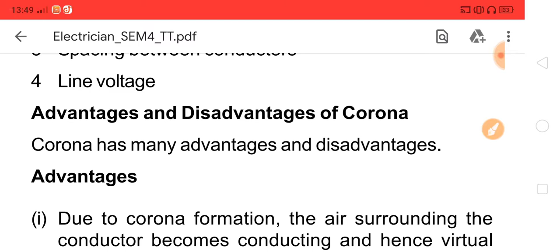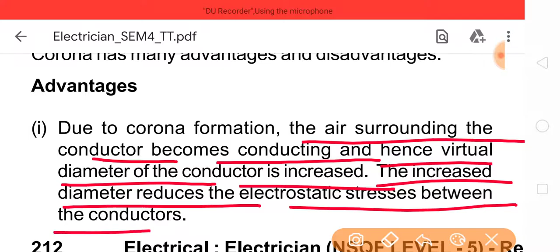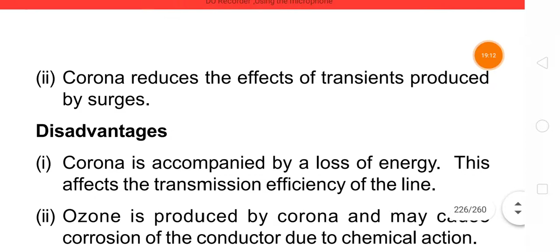Advantages and disadvantages of corona. Corona has many advantages and disadvantages. Advantage: due to corona formation, the air surrounding the conductor becomes conducting, and hence the virtual diameter of the conductor is increased. The increased diameter reduces the electrostatic stress between the conductors. Corona also reduces the effect of transients produced by surges.